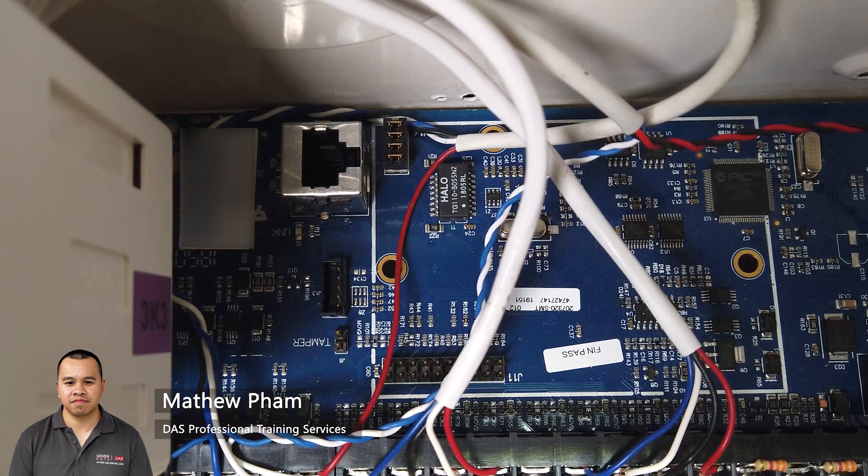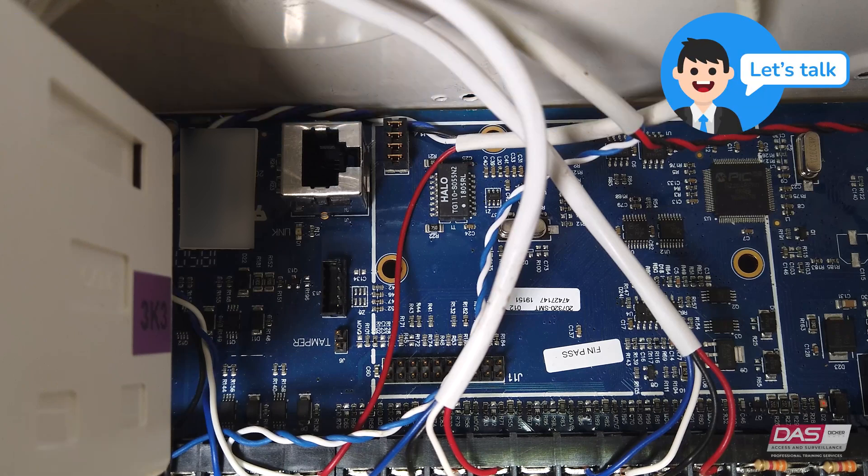In this module we will learn how to enroll devices into the panel. When adding any new devices into the panel such as code pads, hardwired zone expanders, wireless zone expanders, output expanders, and smart power supplies, they will first need to be enrolled so they can be programmed and supervised. The enrollment procedure discovers the serial number of the new device and adds it to the panel's device database.